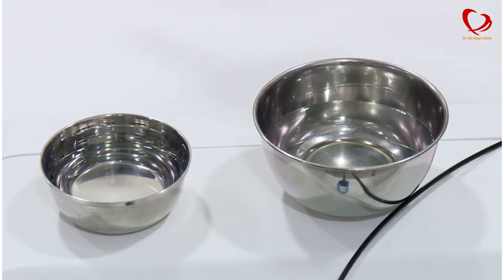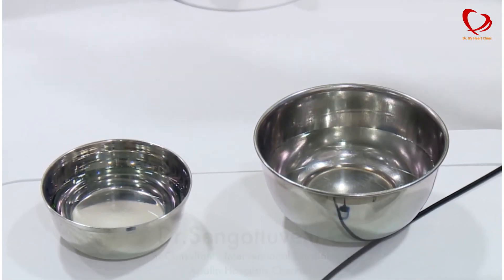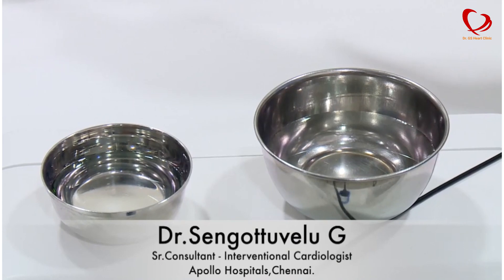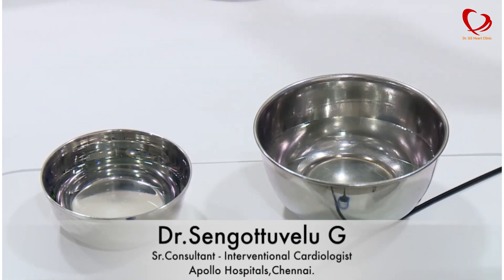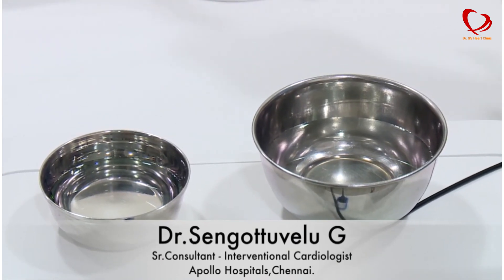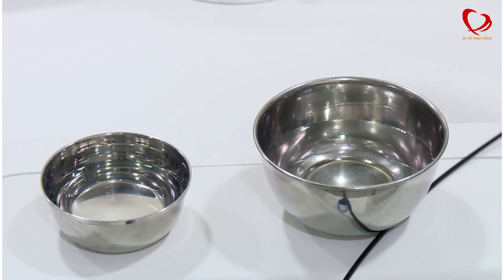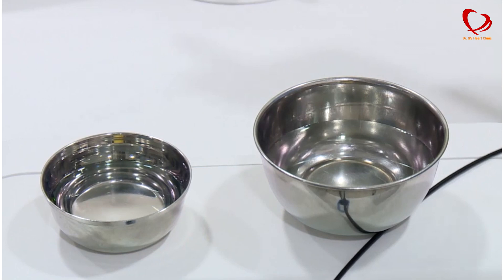The settings here — the fluence, which is the total energy delivered, is 40 mJ per millimetre squared, and the repetition rate is 40. We will start at 40-40 and look at the saline now. I am going to set the laser ready.